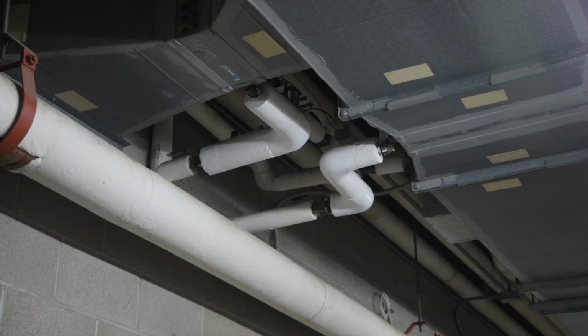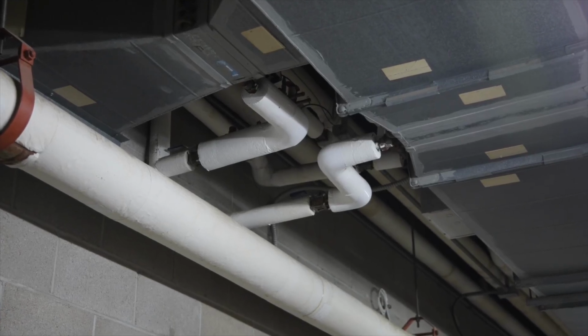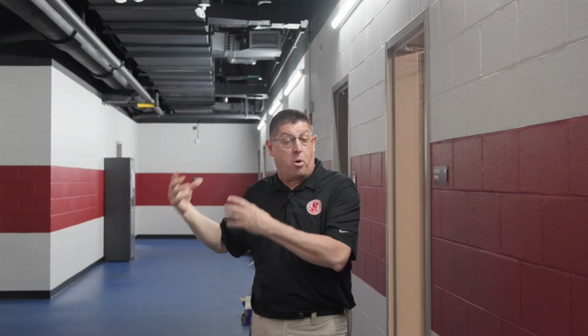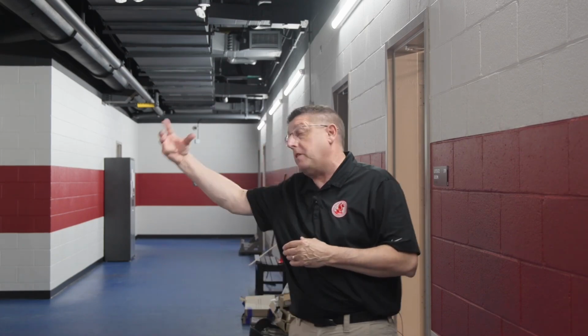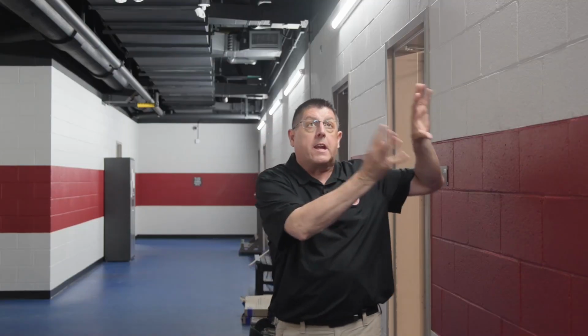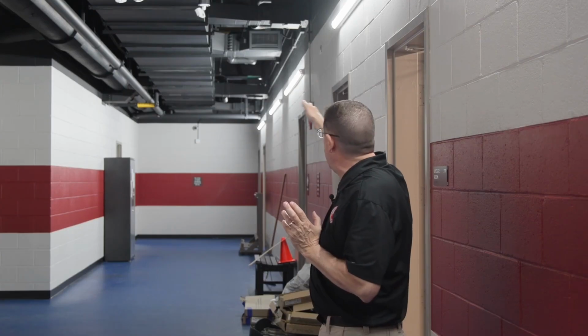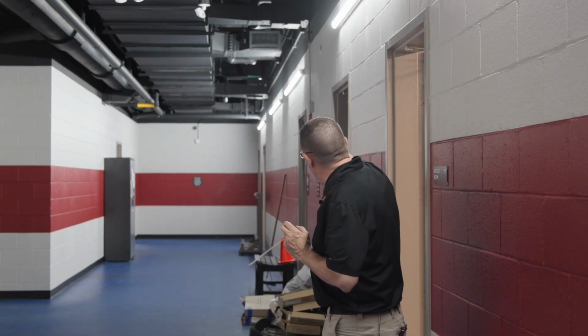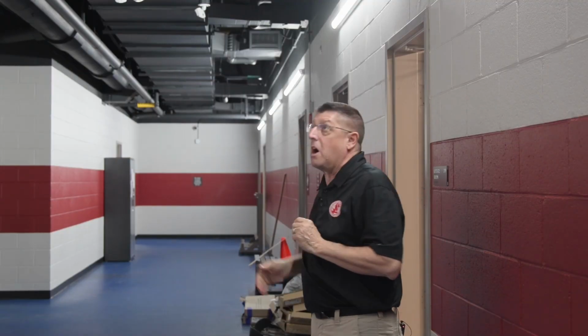So as an aid, we go through a variable air volume or some form of downstream distribution point. We throw in a small radiator like we have above us. And in that case, from the boiler, I can provide boiler water, superheated water. So when the superheated water hits the cool air, I've got tempered air, let's say 90, 95 degrees instead of 180 or 150 from the heat side or 55 from the cool side. I've got that tempered air that gets distributed. So up around across my back, I'll see 1, 2, 3, 4, 5, 6, counting the other zones, different VAVs heading over.